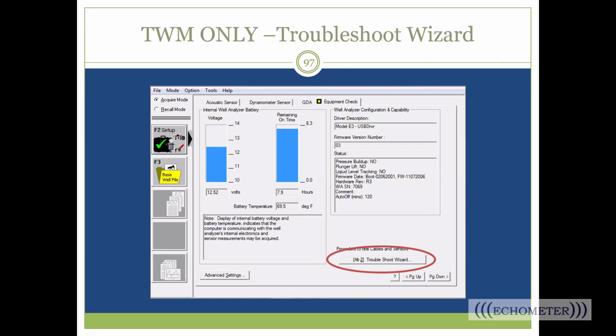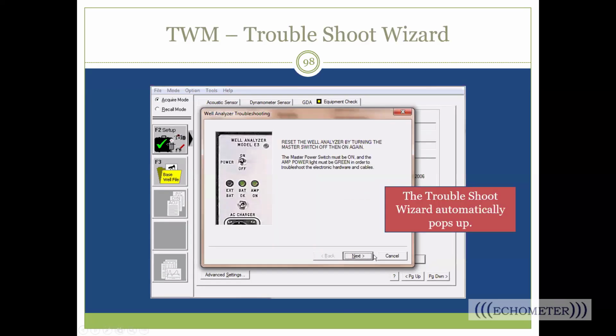Okay, thank you. So when you hook up your well analyzer and you go to the equipment check tab, you'll see this Troubleshoot Wizard here. You click on that button. The first thing the troubleshooting pop-up is going to do is tell you to turn the analyzer off and then turn it back on again. I want to draw your attention to this little panel right here. Here's your power on and off switch, and then you have these 3 lights. These are all related to your battery function. The battery OK light should always turn on and be on if you have the well analyzer turned on.